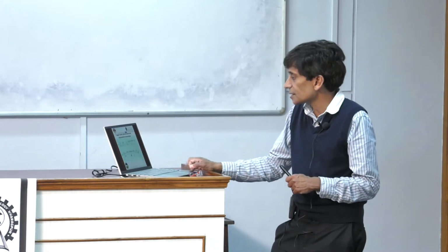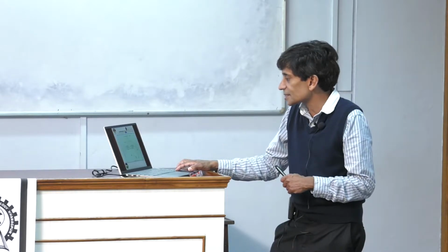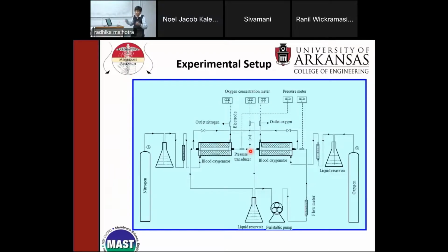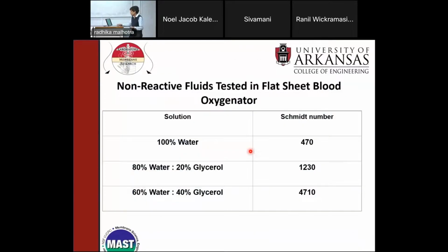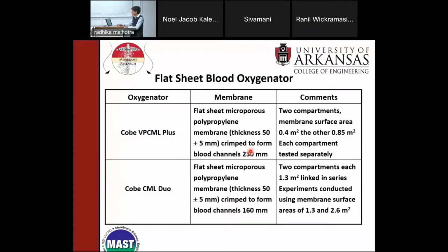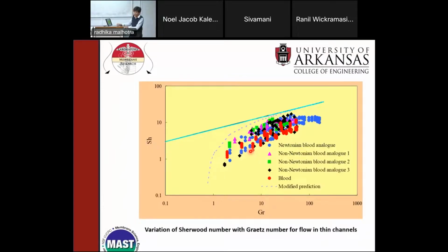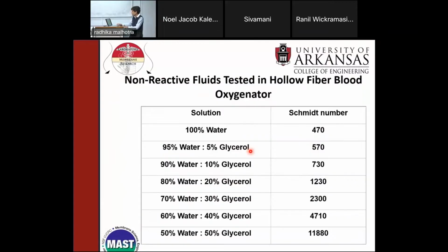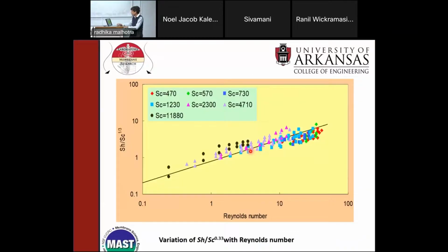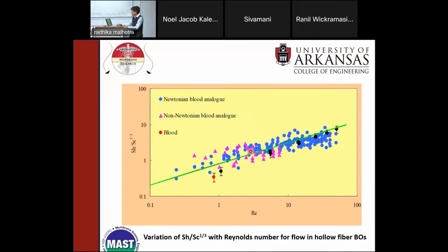And this E is an enhancement factor, okay? And I talked about how we could do this. This is the experimental setup. I said typically there's an oxygenation and deoxygenation run in parallel. This is done in any biomedical lab, and you'd use some sort of model blood, sheep blood or bovine blood. And I talked about various solutions that we could use. We talked about membrane surface areas for neonatal and pediatric blood oxygenators. And I think we stopped somewhere about here at the end of these correlations.